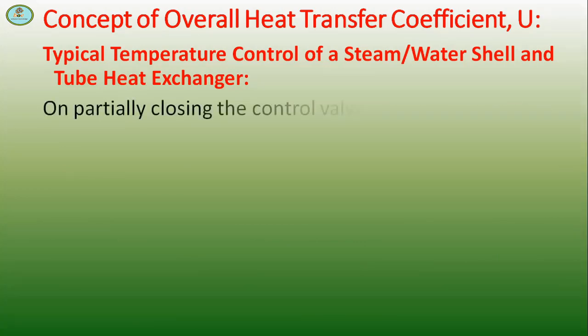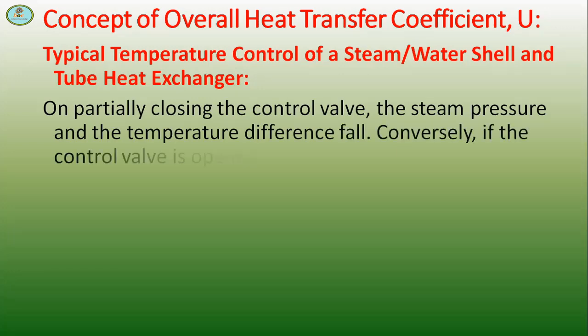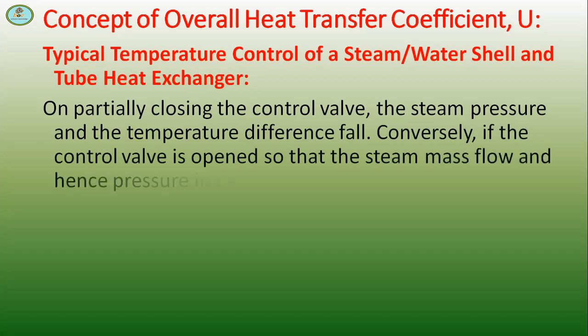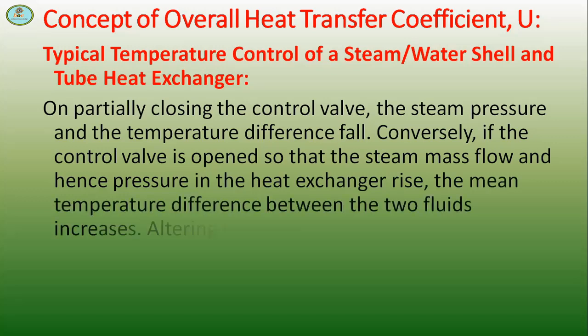On partially closing the control valve, the steam pressure and the temperature difference fall. Conversely, if the control valve is opened so that the steam mass flow and hence pressure in the heat exchanger rise, the mean temperature difference between the two fluids increases.